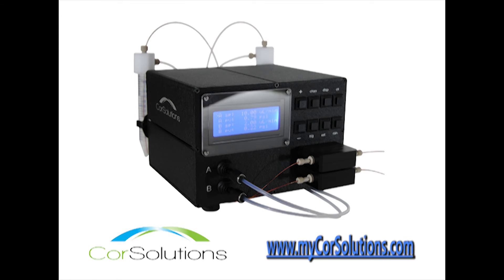New Wave pumps arrive calibrated for aqueous solutions and can store additional calibrations for different fluids. The New Wave offers both digital and analog outputs for data logging.